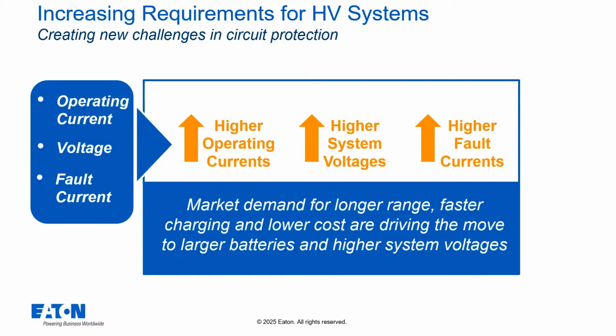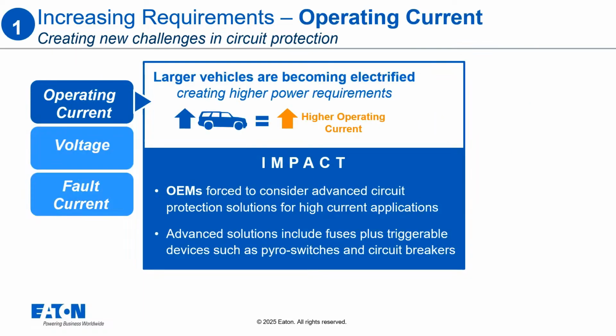Let's start with operating current. With the move to larger batteries and higher power, the continuous operating currents in EV circuits are going up. The big impact here is that vehicle manufacturers are being forced to look at more advanced circuit protection solutions, especially for those higher current applications. It's not just fuses anymore. We're seeing advanced solutions that might include fuses plus triggerable devices like pyro switches or circuit breakers.